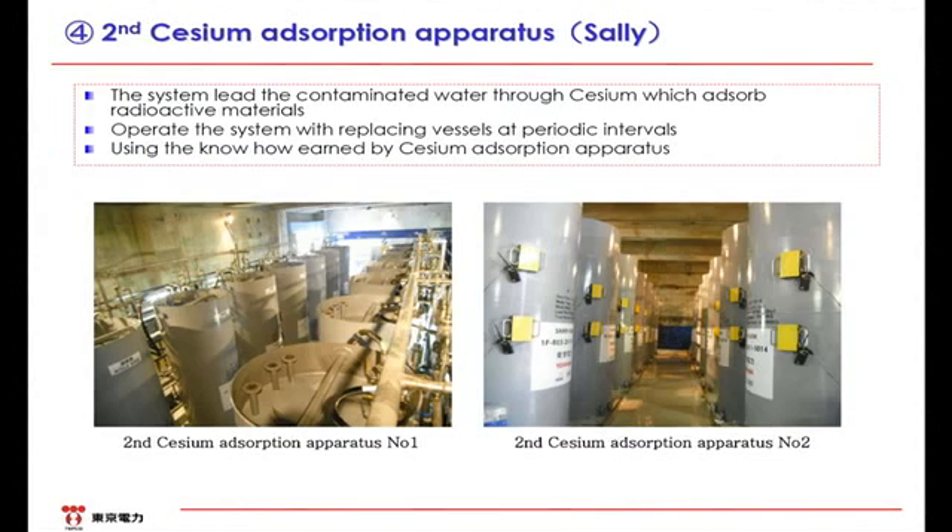The structure of Sally is similar to that of Kurion. Zeolite is placed in vessels. Likewise, when the water goes through it, cesium, a radioactive material, is adsorbed. After cesium is adsorbed, the tower is replaced every two to three days. We have been operating Sally since August. Basically, Sally is a little bit easier to operate compared with Kurion. Thus, we mainly use Sally for the water treatment.